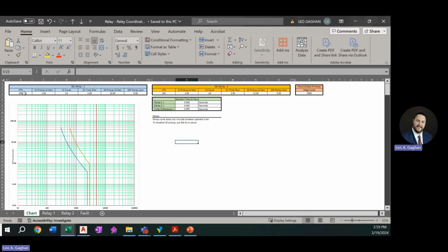So let's say, for example, your relay didn't have a CTR 240, it had a CTR of, say, 400. You can plug that in, you see how the curve moves. Let's put it back to 240, just to get things simplified here. Our 51 pickup in amps secondary is currently set to 1. If we were to increase this, we would see this inverse time of the curve move to the right, but also move up. So let's say I punch that to 1.5. We can see that there, it moved to the right, but it also moved up.